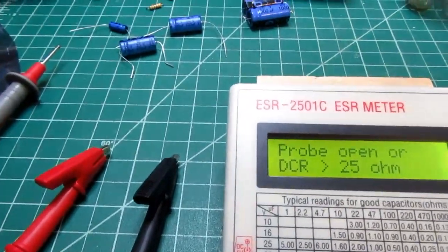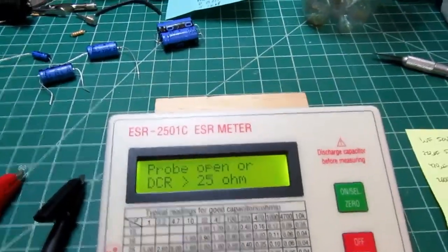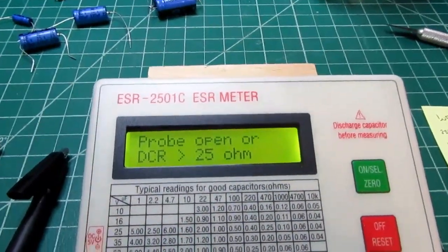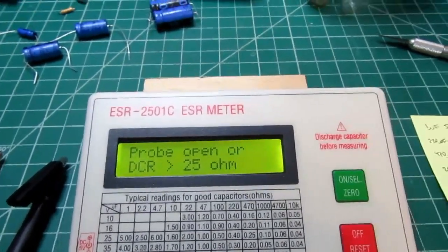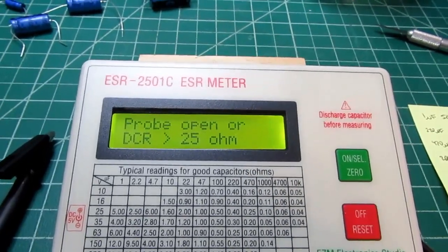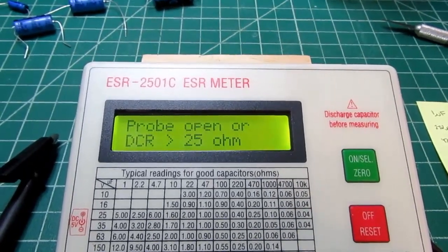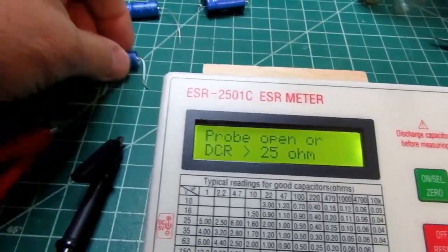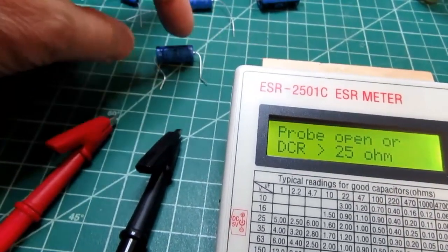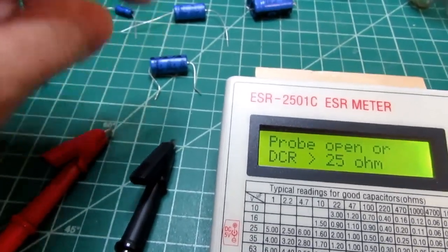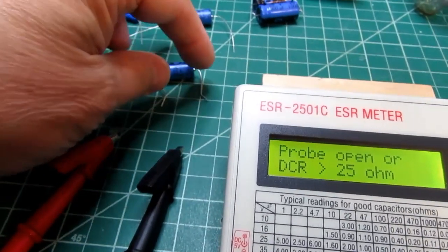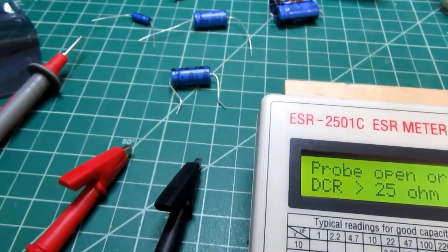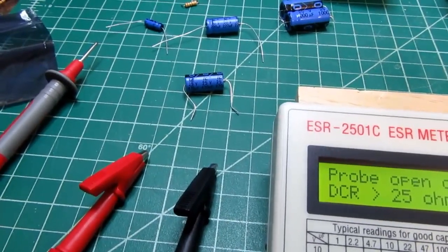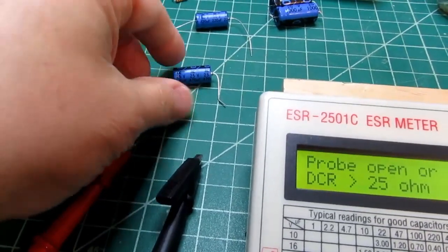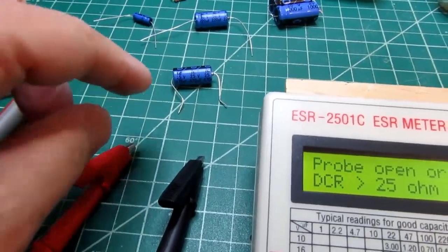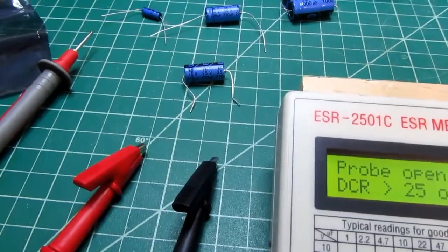With DCR, a higher number is good. You want it to be infinity if you can arrange that, because the DCR is telling you the resistance between the leads of the capacitor. A capacitor with a DC signal on it should have, not infinite, but a really high resistance. If you start getting a lower resistance, that's indicative of a failure of the internal structure of the capacitor.